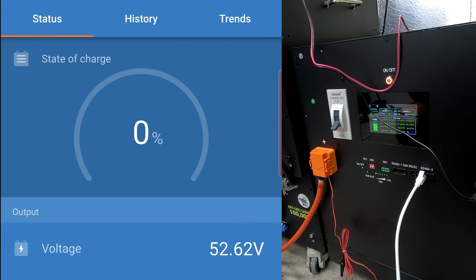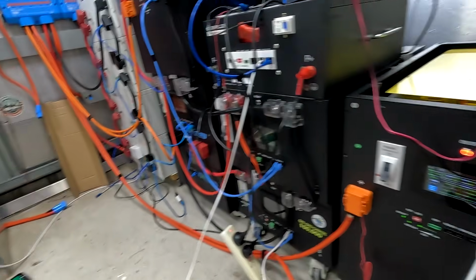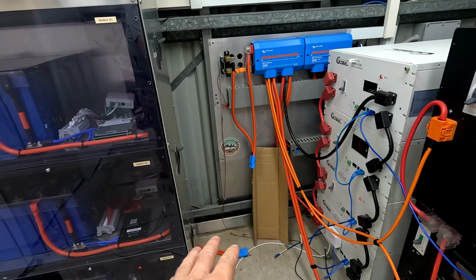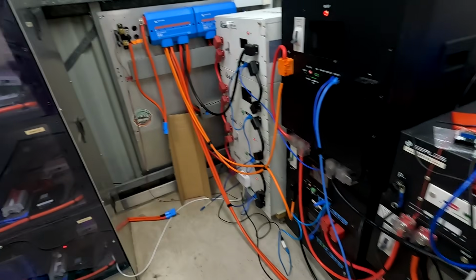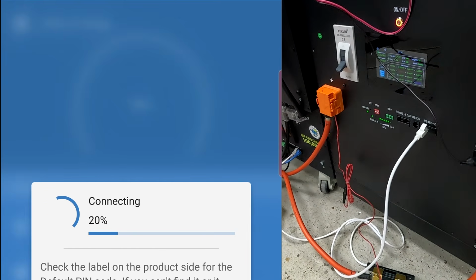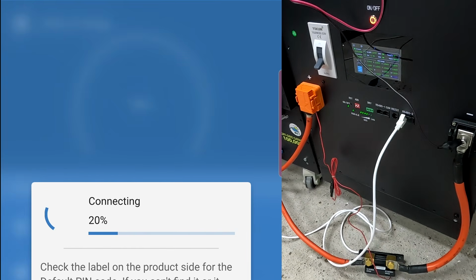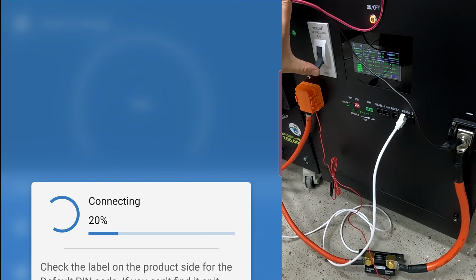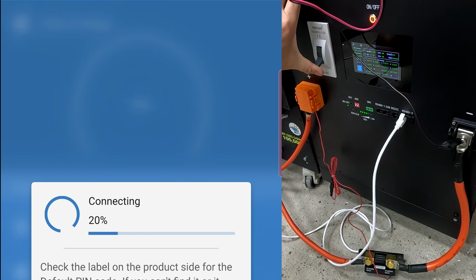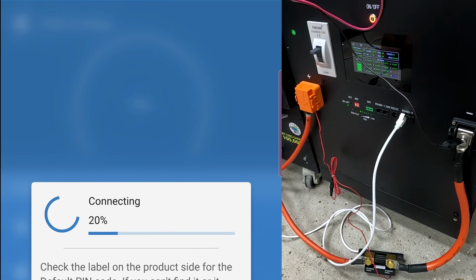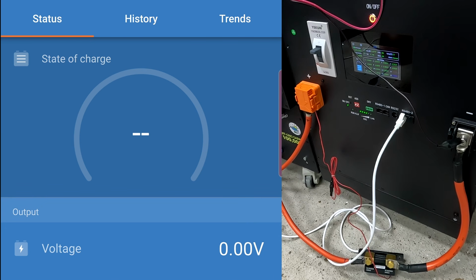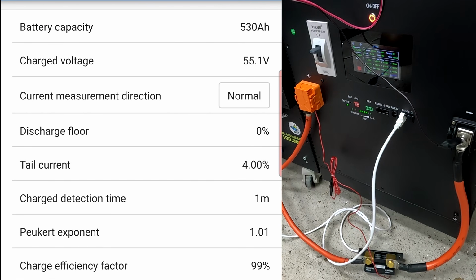Alright, it measures the battery voltage. You know what, I have to disconnect the Anderson connector which is connecting the Powerwall to the battery shelf. That's why we had such a low voltage shown in the Smart Shunt, and now you can see we have lost connection altogether. But I'm turning on the battery now, so we get the full voltage on the Powerwall, and this should give us the full battery voltage of 57.38 volts now. That was a good test actually, showing the lower voltage of the battery shelf.